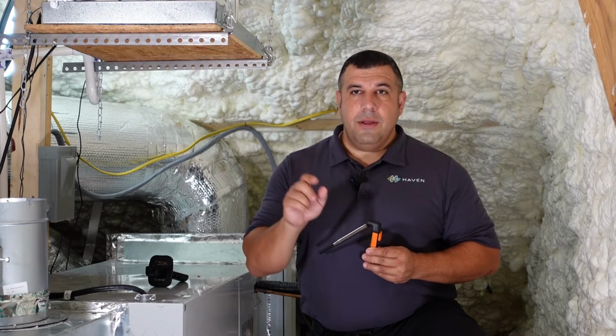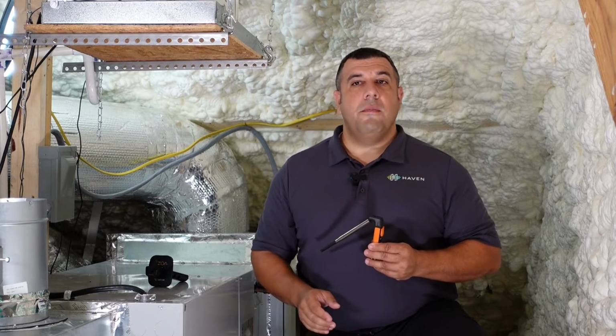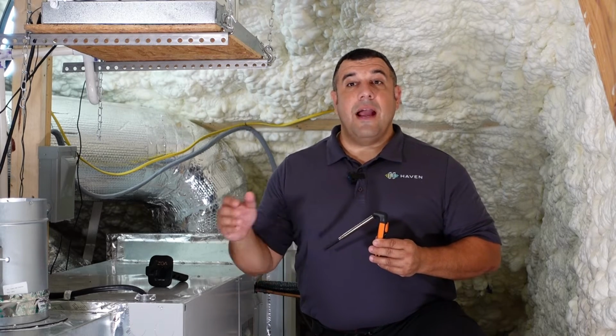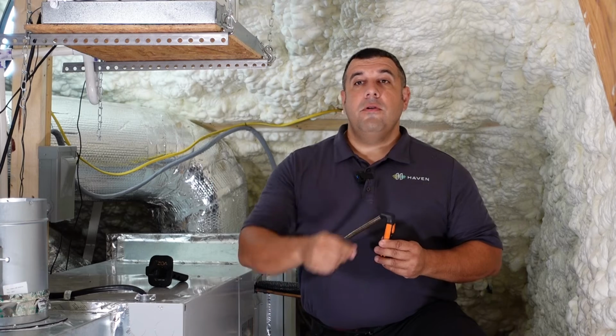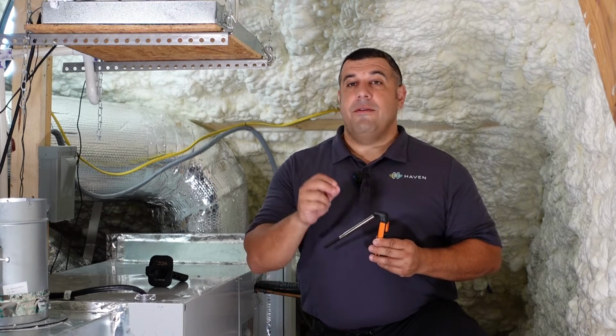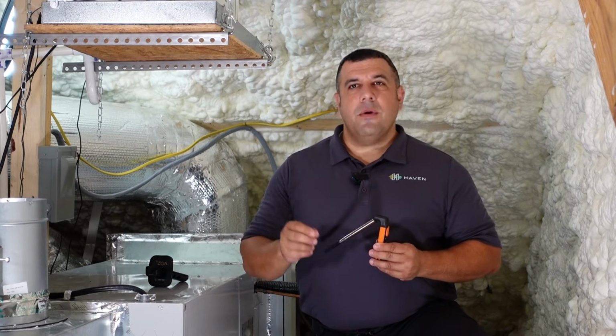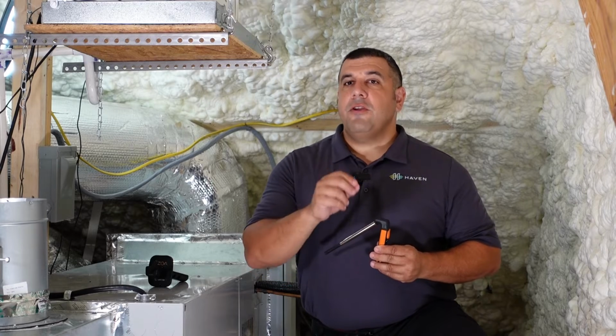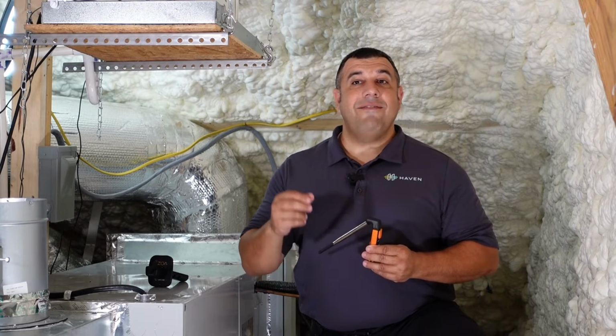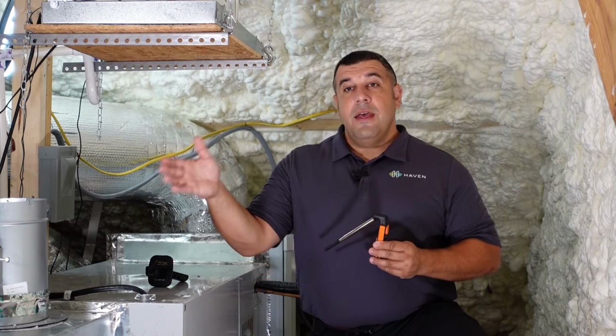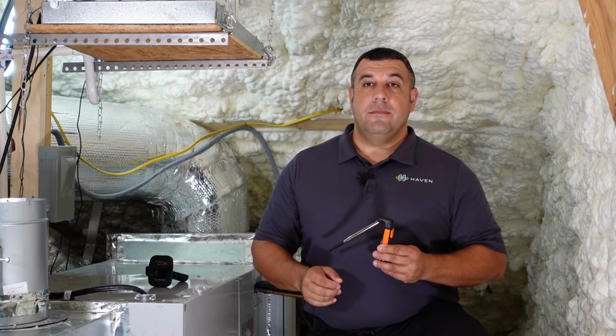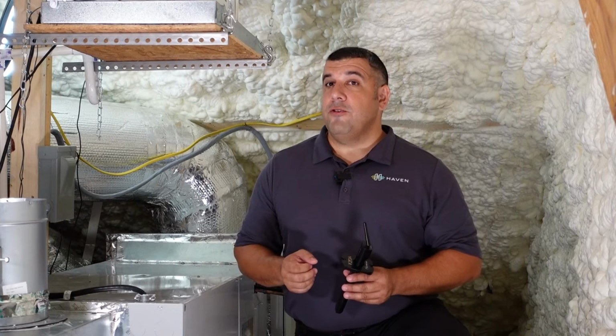Make a small hole in the duct close to where you want to install the monitor. Doing this now with the air handler fan on can help you confirm that you're achieving the minimum air velocity. Otherwise, you may want to try another location. If pressure is too high, the system will likely have airflow problems that need to be addressed before completing the installation. Depending on what version you have, you may have slightly different parts included.